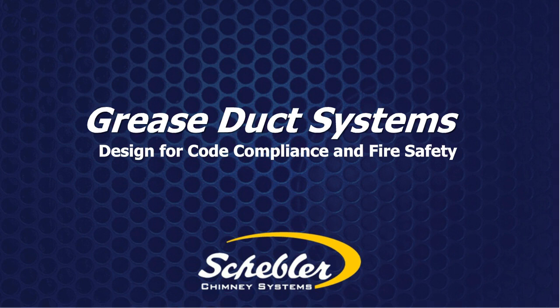So for instance, it's not uncommon for us doing a large system, as I showed in the Mass General project, where we did not design the last few sections of the ductwork that connect to the hood because the hood had not been set yet. So the majority of our system was shipped, delivered, received on site, and installed, and then once the hood was finally set, we received final confirmation of those locations to pick up off the hood for the remaining parts, and then we designed, built, and shipped those within 1 week working time.